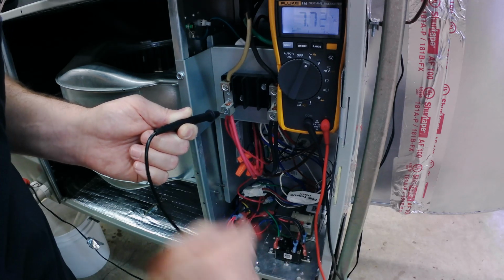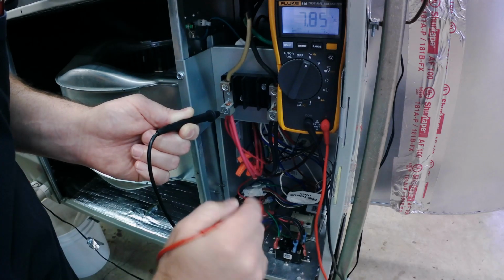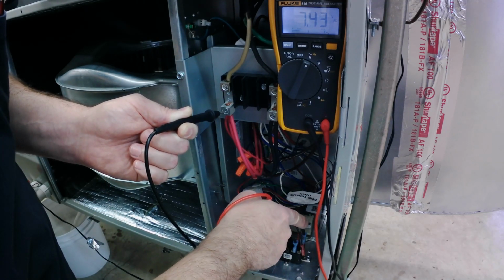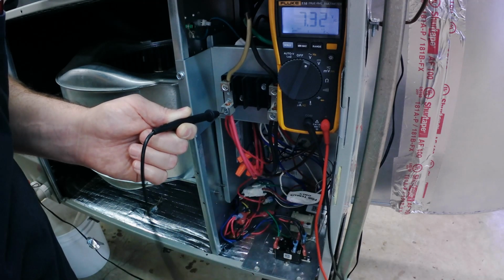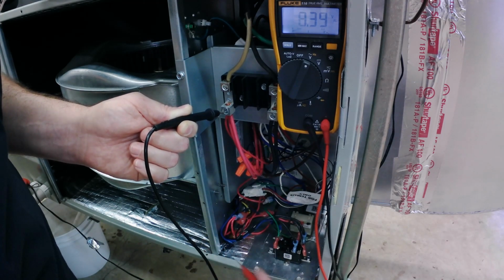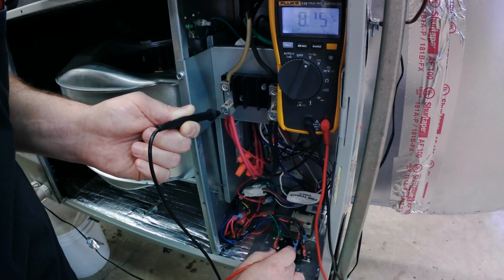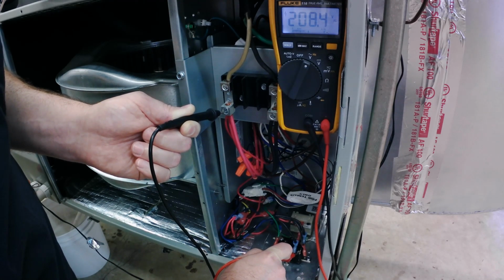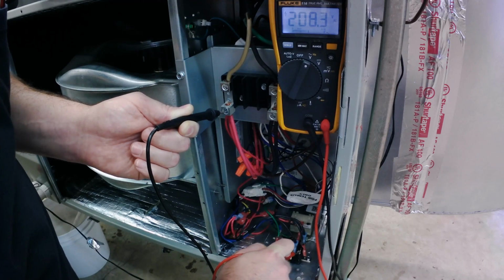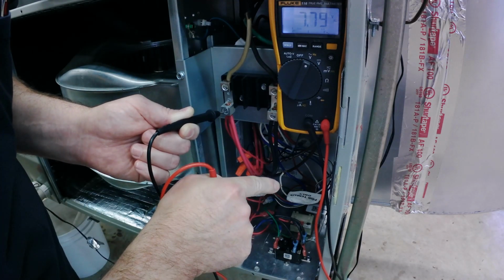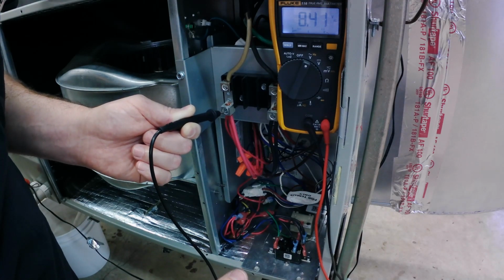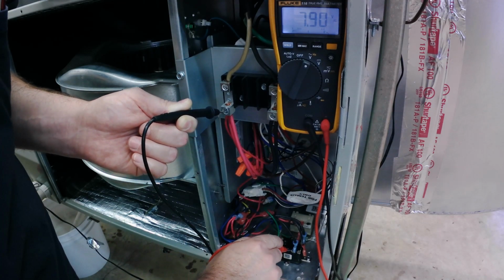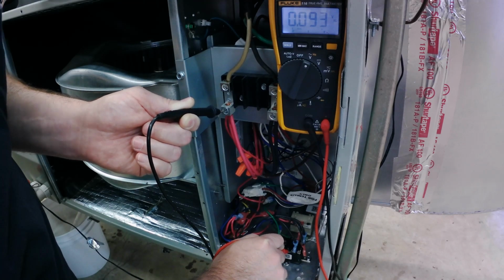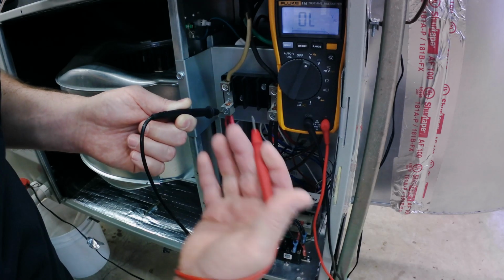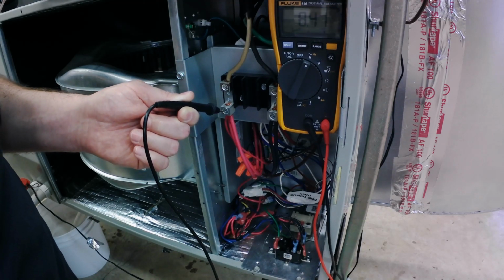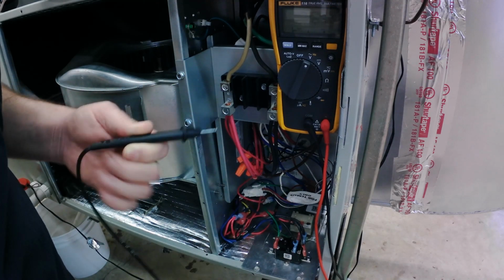But work with me. I've got power going into that relay, and if I check, that was terminal 2 on the normally open switch, which it should be closed now that I've got power for G. If I check the other side and I've got the same 208, then that means that power went into the switch and then back out. If you were to check power in and then when you checked it coming out you get 0, that means that switch has not passed that power. Power going in and not coming out, that's a bad switch.